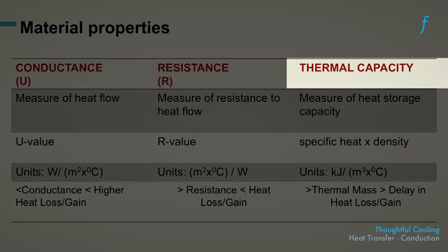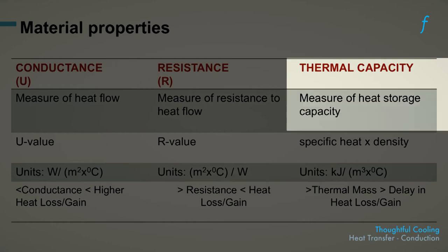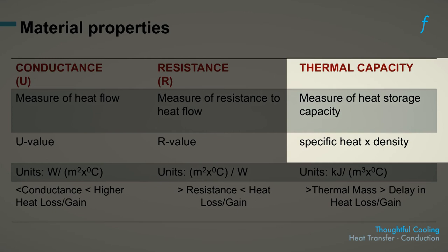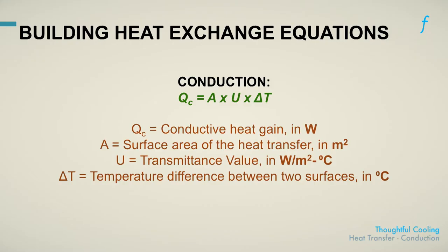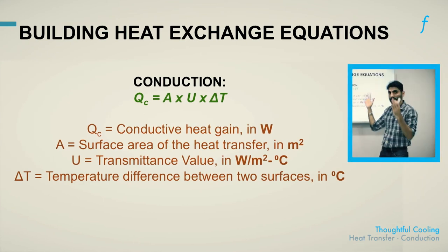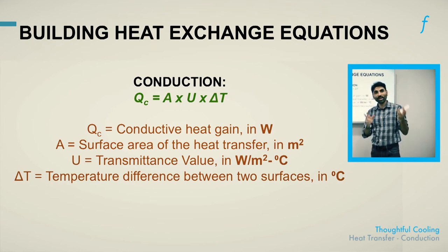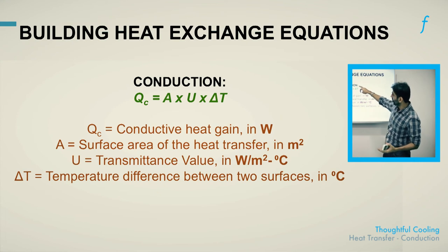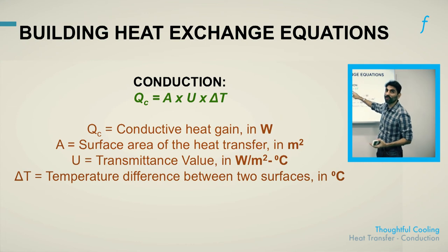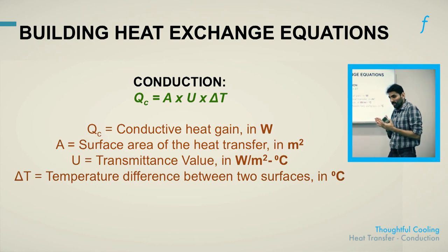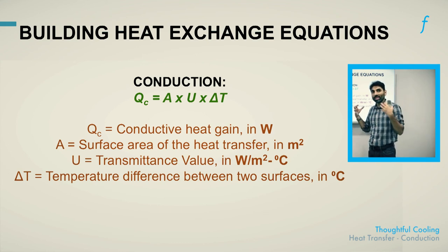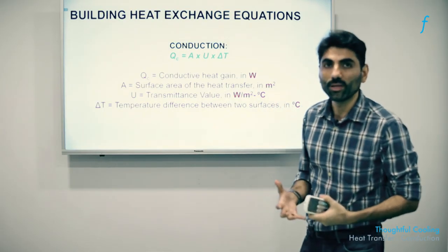Thermal capacity, as emphasized, is a measure of the heat storage capacity of a material, not its ability to delay or conduct heat. The objective for a thoughtfully cooled building should be to use a material with high thermal mass so that heat gain is delayed as much as possible. The amount of heat gained or lost through conduction is directly proportional to the area available for heat transfer, the U value, and the temperature difference. The higher the U value and the greater the temperature gradient, the more rapid the rate of heat absorption or rejection.